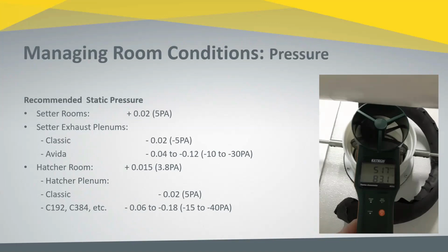Okay, thanks. Another question came in from Irfan. He asks, what is the effect on DOC if we set the room pressure too high? If we set the room pressure too high, it makes it a little bit tougher to maintain, because a high room pressure generally forces doors or traffic doors into the room.